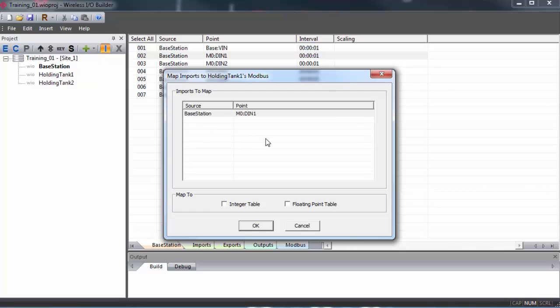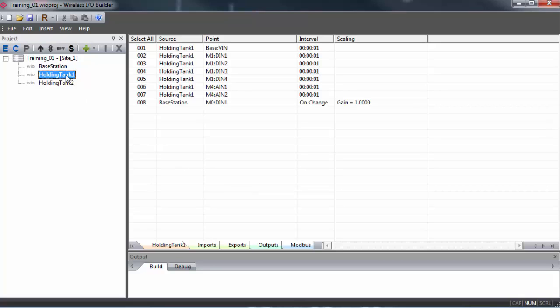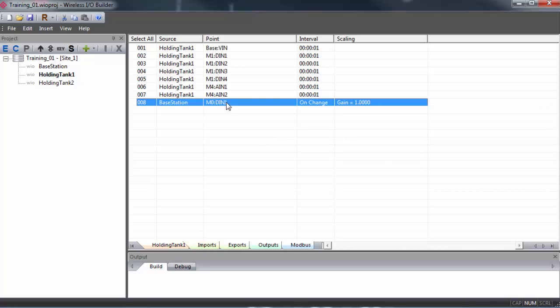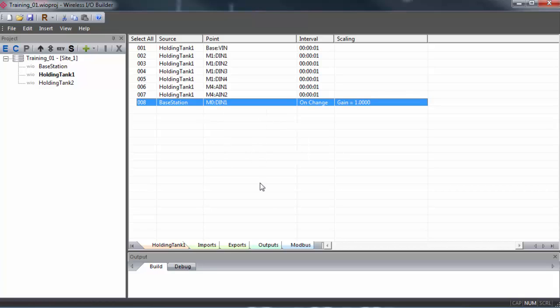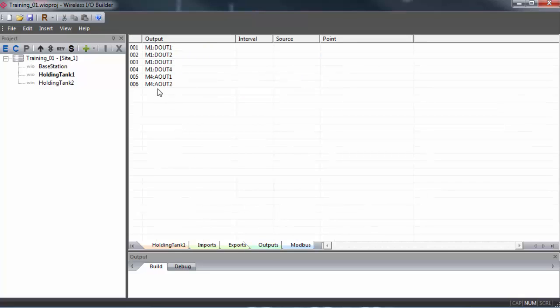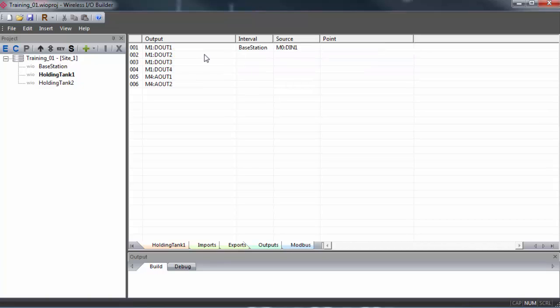We get a confirmation window with the source group and the points we're about to map. If you're sending Modbus data, you can specify if you want to map it as an integer or a float. Click OK. Now we can double click on holding tank one and go to the imports tab and we can see the entry here for the point that we just brought over. Source Base Station Point Digital Input 1. We'll select this point, right click and copy. Then go to the output tab, select the output one, right click and select Paste Output Source. Now we can see that the digital input one from base station is the source for output one on holding tank one.